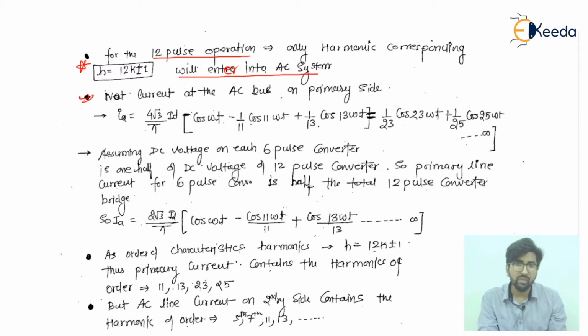This will be okay. Now if we talk about the net current at the AC bus and the DC bus, if you talk about the AC bus, on the primary side, then we will have this current. This is the per phase current IA, and this is 4√3 divided by pi into ID. This is a combination we have actually found from the above 6 pulse converter current and the below 6 pulse converter, and we have added and simplified this. Then we are actually getting this.